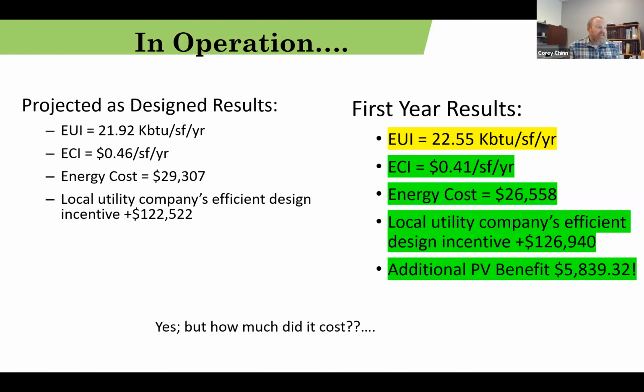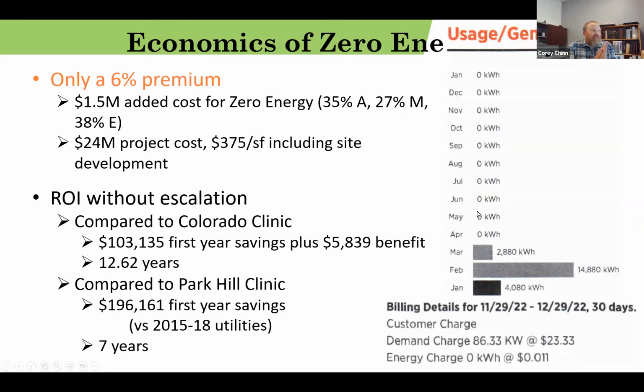That's pretty awesome. And how much did it cost? It took about a 6% premium over standard design in order to accomplish this. The contractor, Brian Construction, did a cost analysis on their own. This wasn't us engineers trying to advocate for it. They came up with a $1.5 million added cost for this project to go to zero energy. 35% of that was architectural, 27% mechanical for our geothermal that we always hear is way too expensive, and 38% electrical, which includes the cost of the on-site PV array.